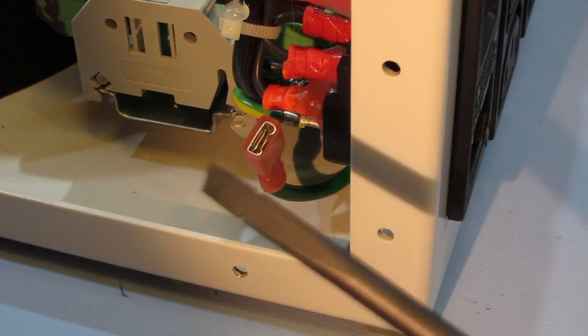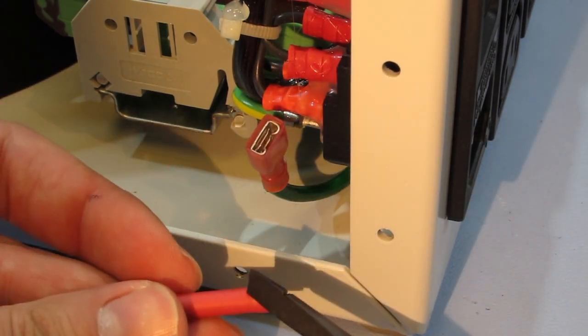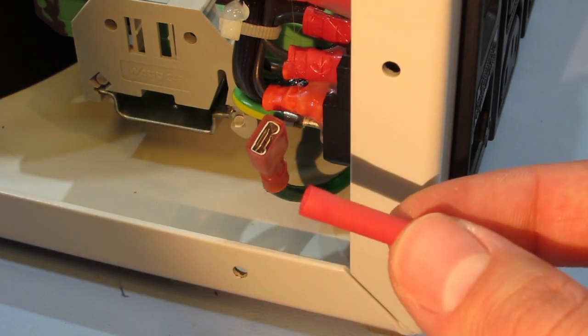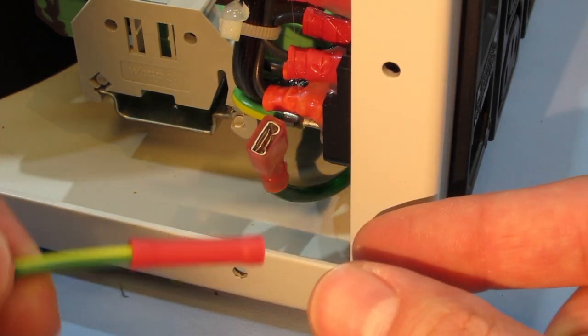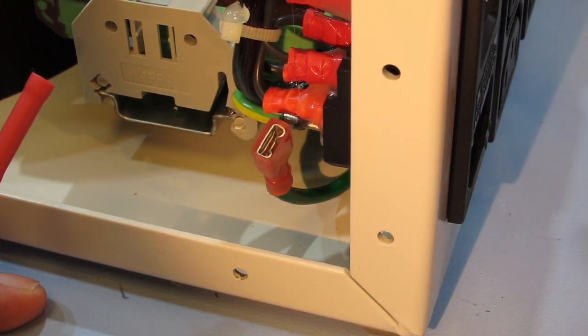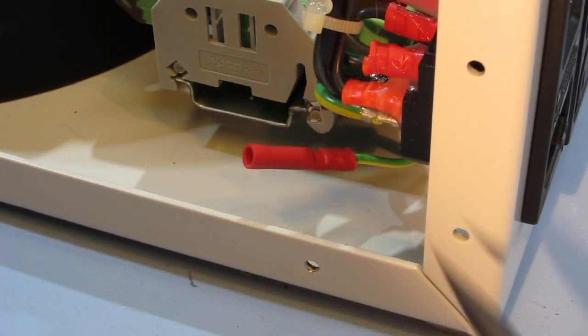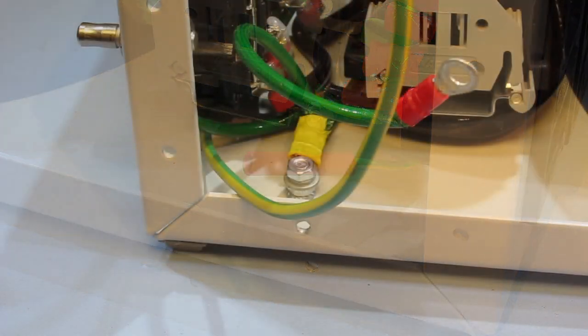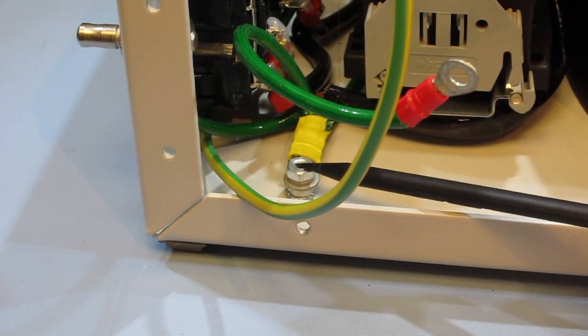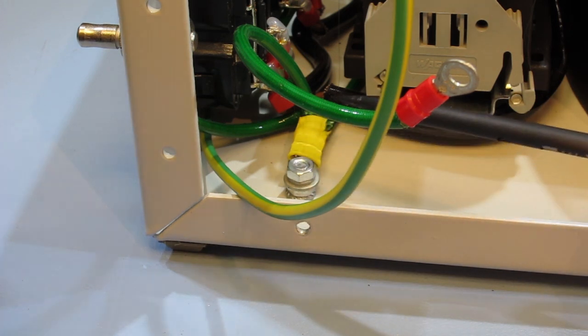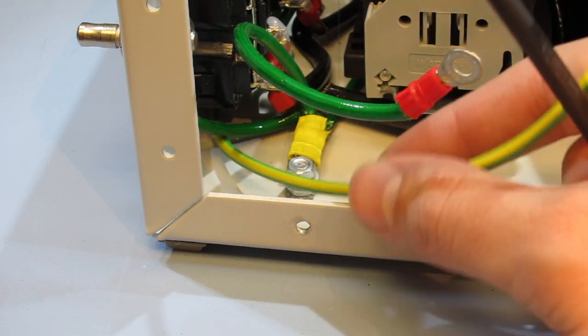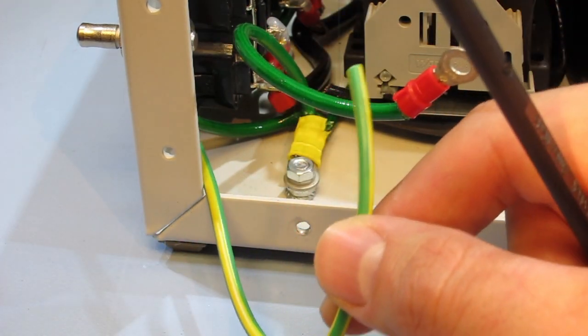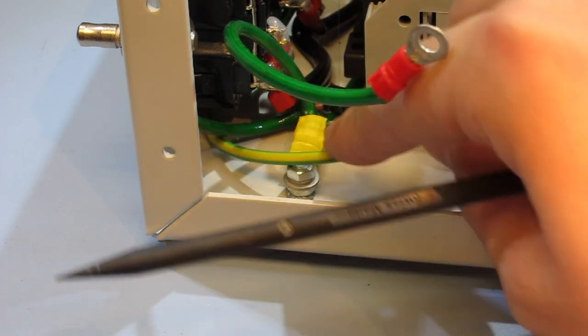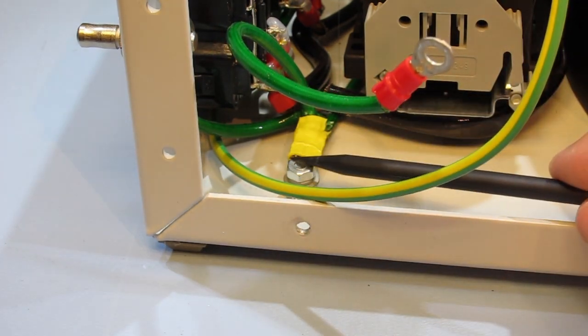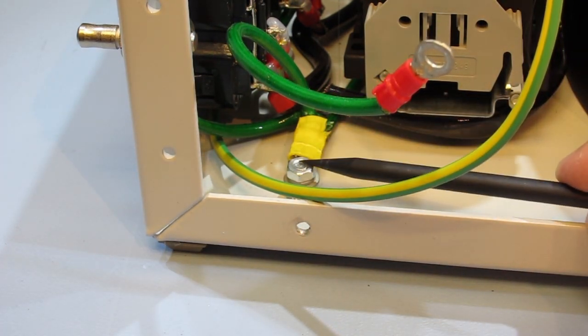In fact, what I think I'm going to do is cut the crimp off and actually crimp on one of these through crimps, and then the earth from the top cover I'll just connect onto here, and that will provide the earth connection onto these IEC outlets. Okay, so you can see I've managed to just get a crimp on the end of that. So here's the other side of the transformer. This is where all the earths are connected in a star kind of configuration. This is the earth cable that I just connected to the AC inlet. That's obviously going to go to that star point, and also the core of the transformer is going to be connected to that point.